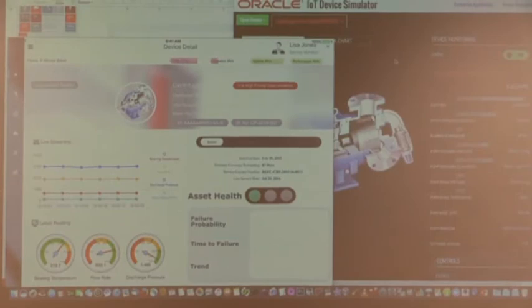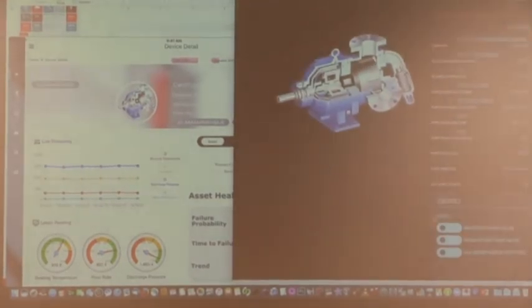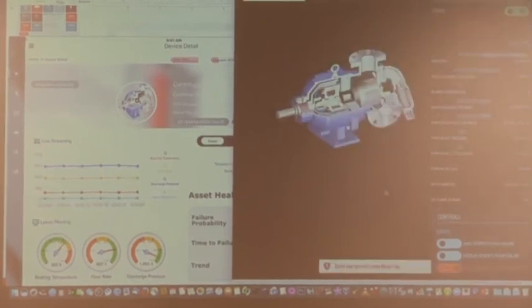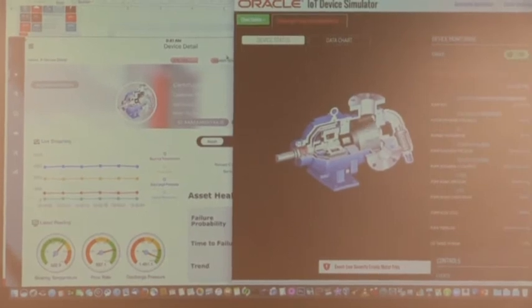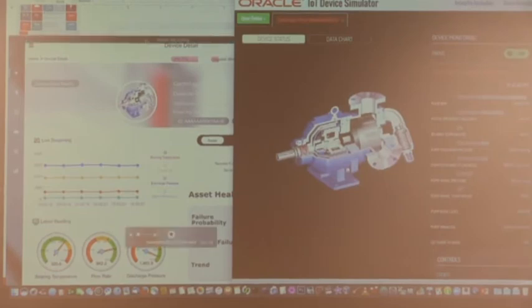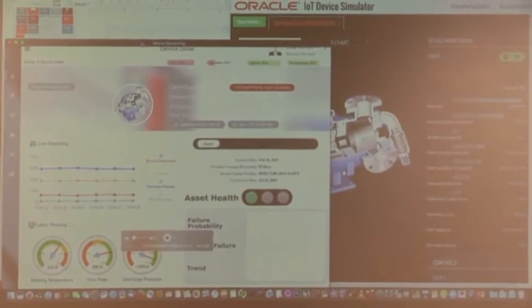Now I'm going to simulate a failure event — simulate the fact that the pump is going to fail. If I simulate a low severity event, I'm saying there's a small issue with the pump. You can see the bearing became slightly red in color, meaning there's something going on with that bearing. In a matter of a few minutes or seconds, you'll see the asset health change from green to amber, signifying that there's an issue with that particular pump.